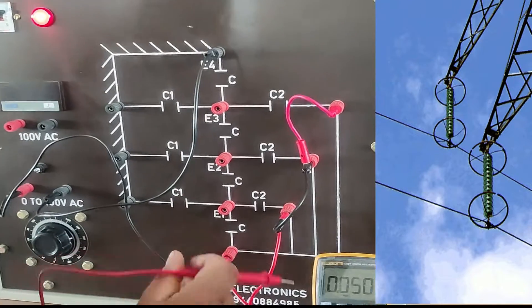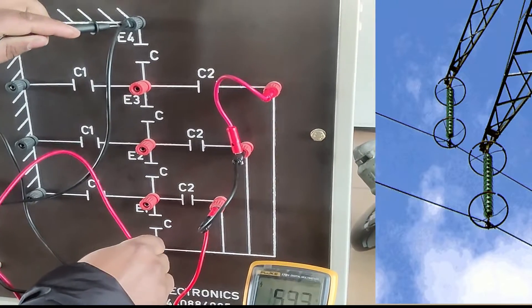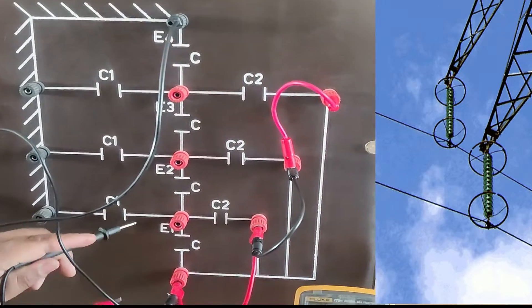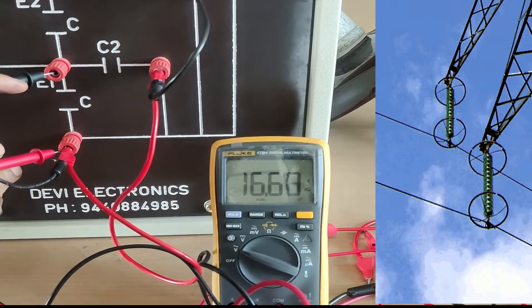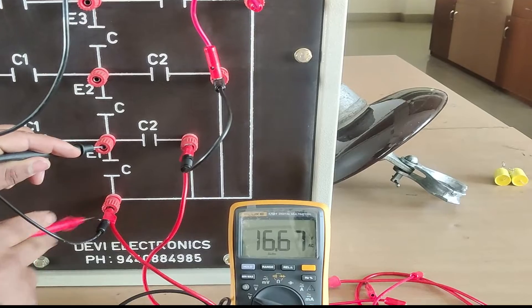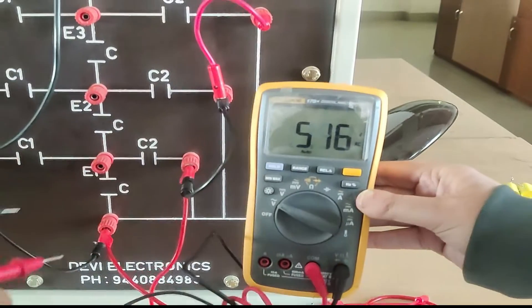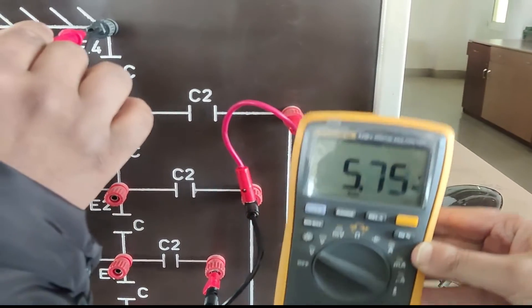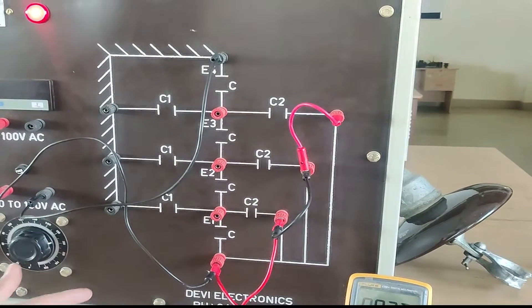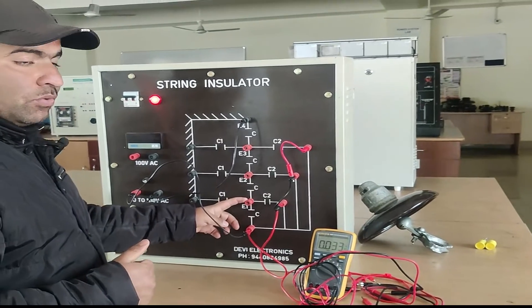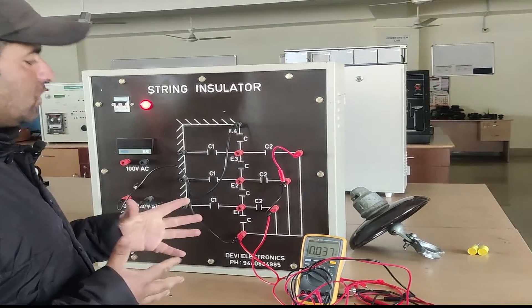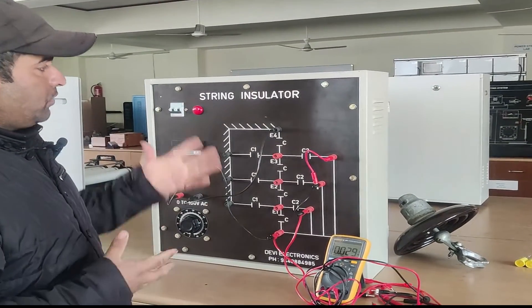We have connected the guard wire creating an additional capacitance to compensate leakage current. We energize the string again at the same 60 volts and check. The voltage across the bottom disc has now reduced from 22 volts to 16.69 volts — much closer to the ideal 15 volts. The second disc shows 13 volts, and as we approach the top, it continues to reduce. The voltage is now more uniformly distributed, and the string efficiency has improved from around 60% to approximately 90–95%.